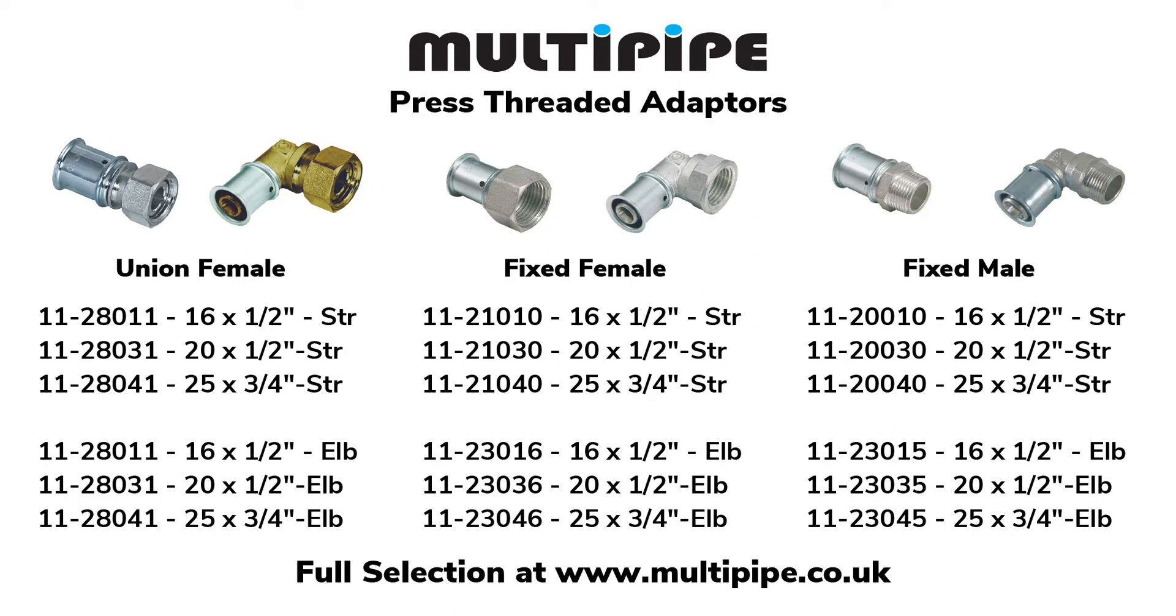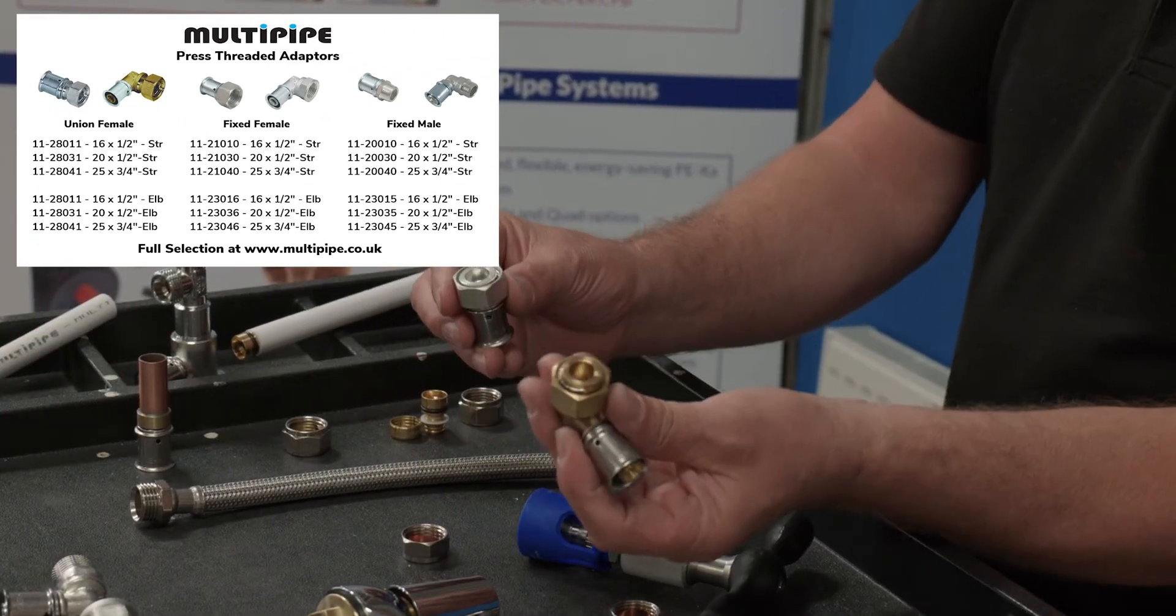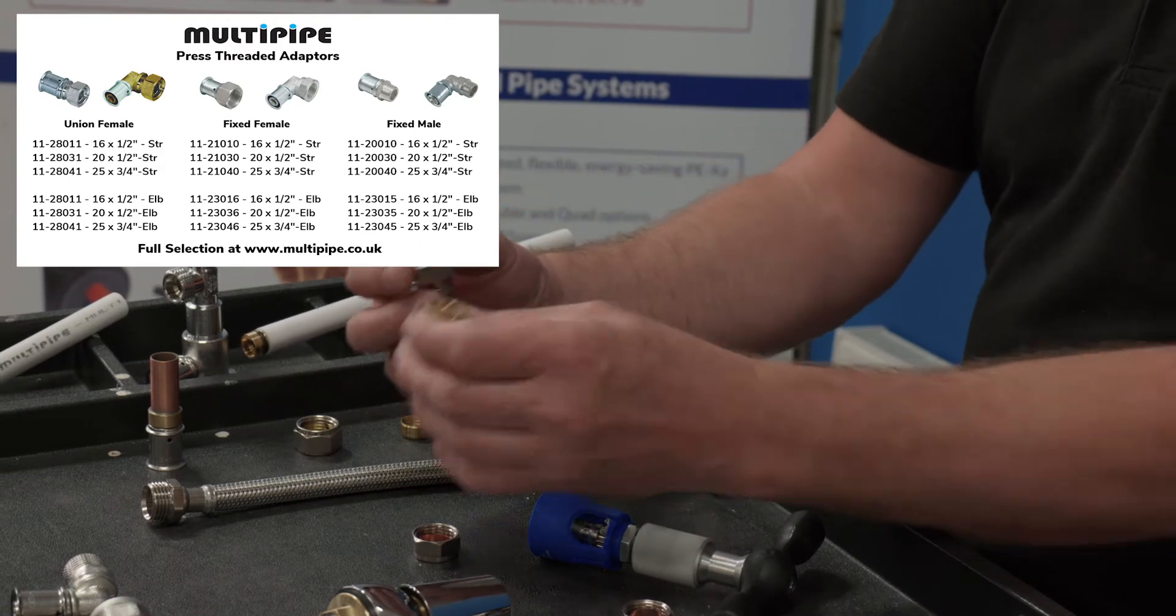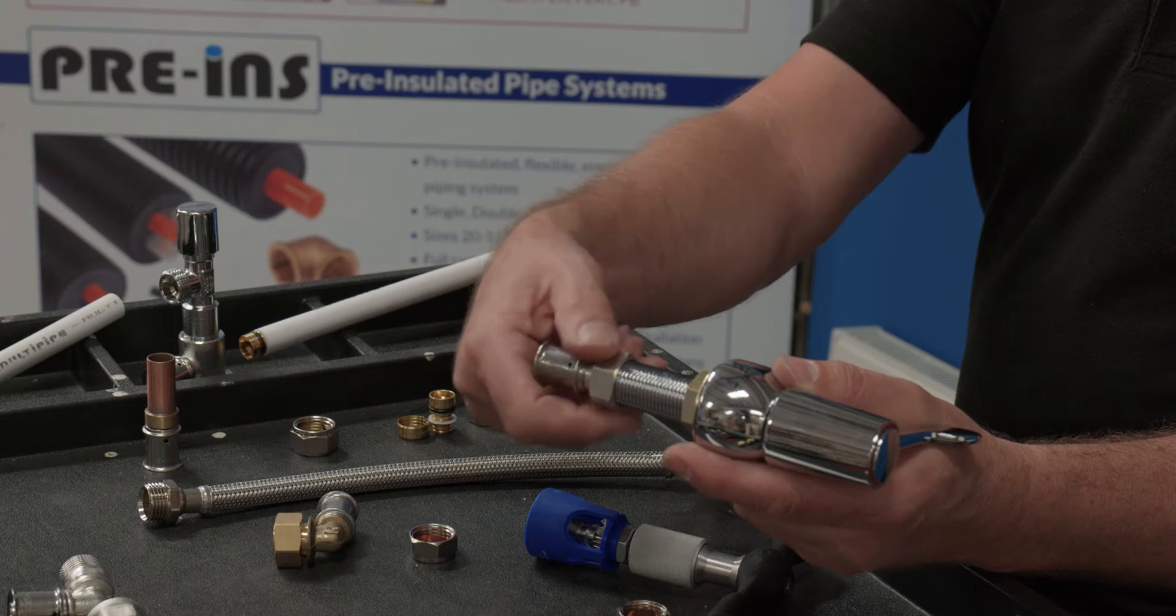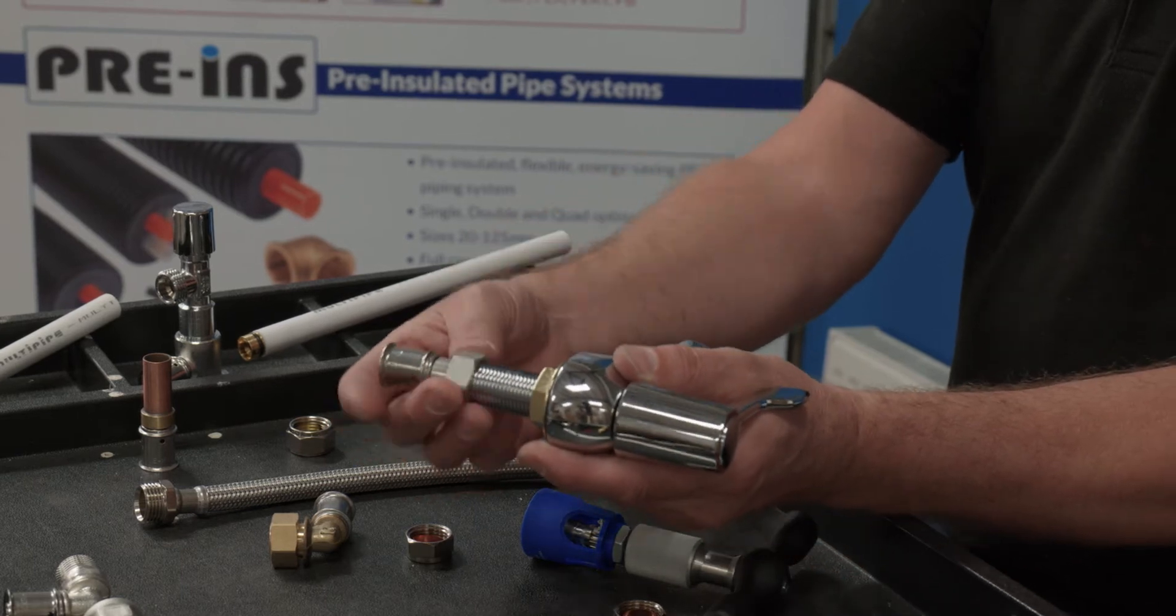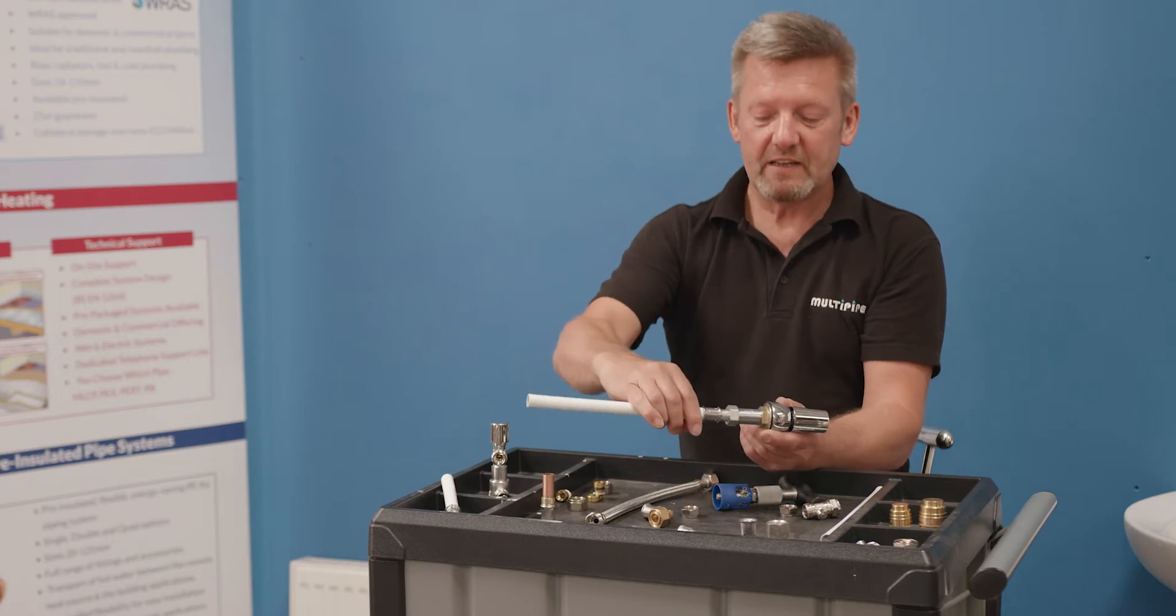Now alternatively, if you didn't want to use this compression adapter, there are some swivel adapters. So these are available in both a bent or a straight version and this will be a flat washer system and this could then take MLC straight onto the bottom of a traditional standard half inch tap and then that particular pipe would just be pressed into place with the normal press gun.